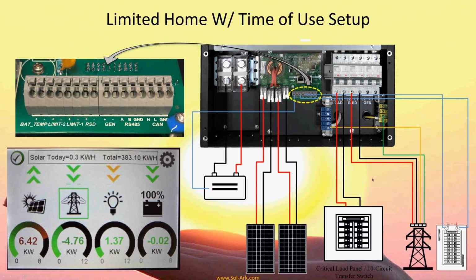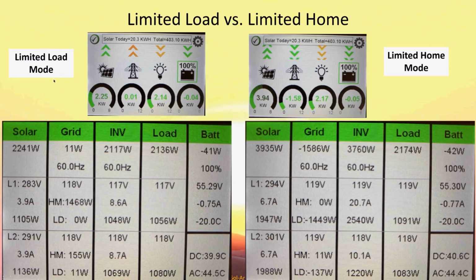Sometimes it can be tricky to get these sensors installed correctly on L1 and L2, since they're directional, so they need to be oriented the right way and in the right sockets. When I'm limited to the loads, I see the loads here, and my load sensors aren't exporting out of the 8K system itself, but I can still see a positive value for home, meaning my home is consuming some more power. That's limited load mode. If I do limited home mode, I expect to see some negatives at the 8K point of view, and near zero at the home. That's the difference. If I'm selling back to the grid, I expect to see negatives throughout, though I don't need the home sensors for that.